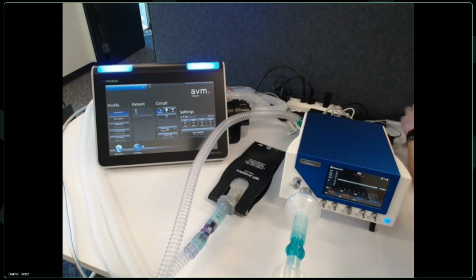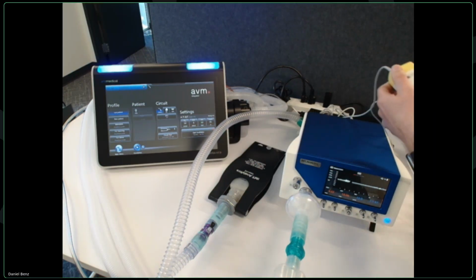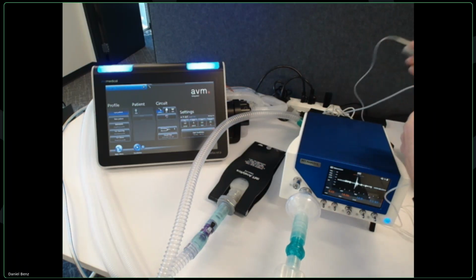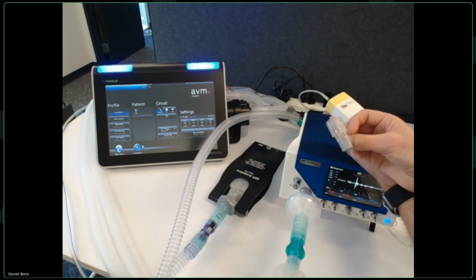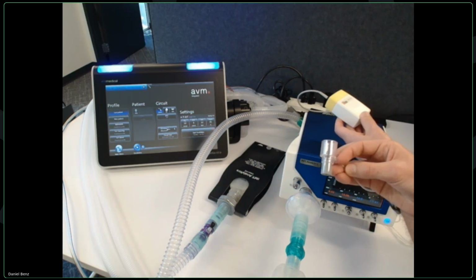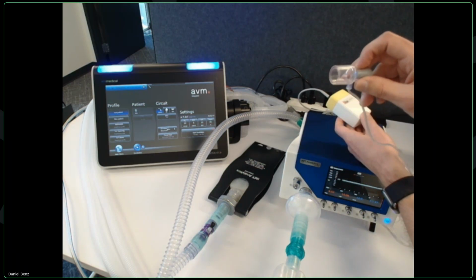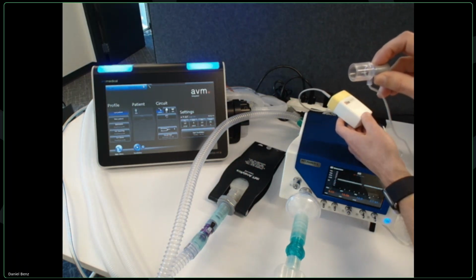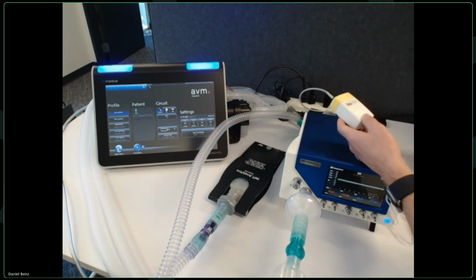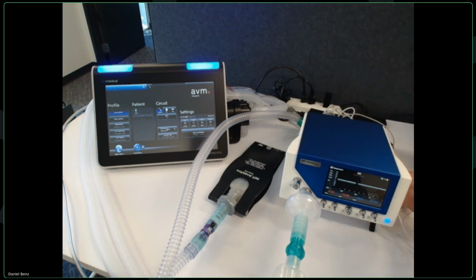The next thing I want to show you is how you can use an application for the ultra low flow channel of the FlowAnalyser PRO. As already mentioned earlier, this ultra low flow channel has a measurement range of ±1 liter per minute and can be used to measure very low flow rates with highest accuracy. So one application for something like that is I have here a capnography sensor. So this sensor can be connected to our ventilator, and it has this little T piece here. And what it does, typically you have that in your circuit system in front of the patient, and then it samples a little flow here through this tiny line here, and pulls some of the gas mix in this sensor, and then measures the CO2. So let's see how we can measure that on our FlowAnalyser Pro.